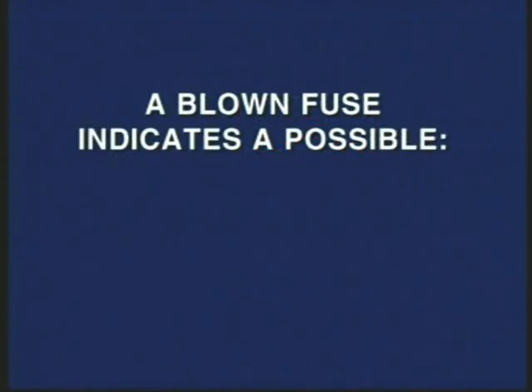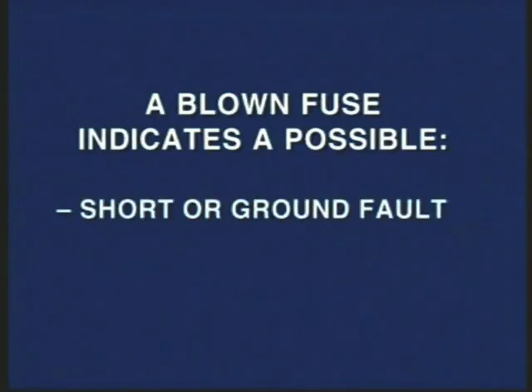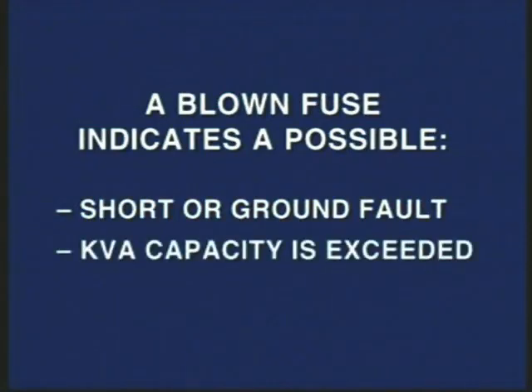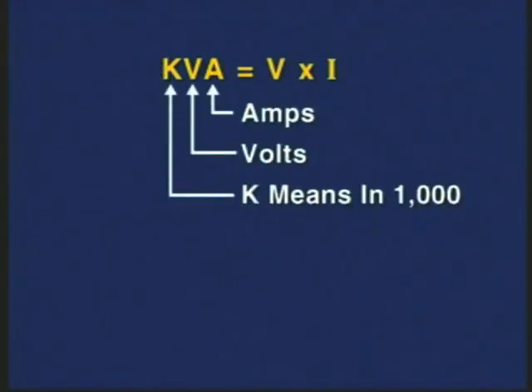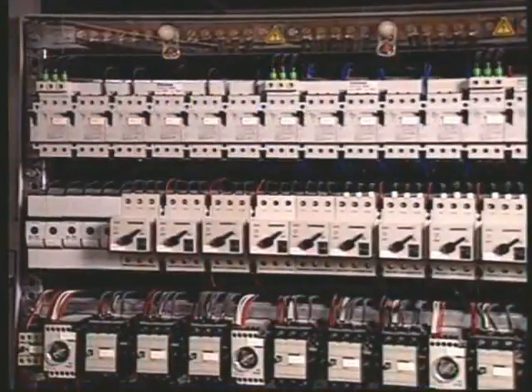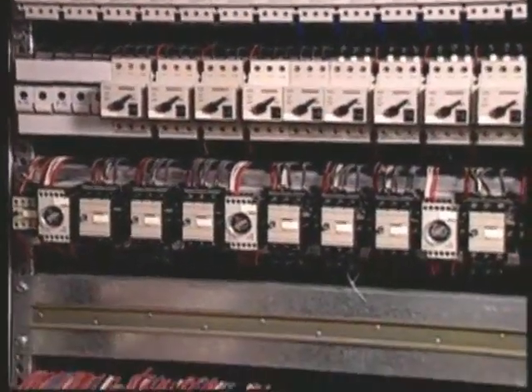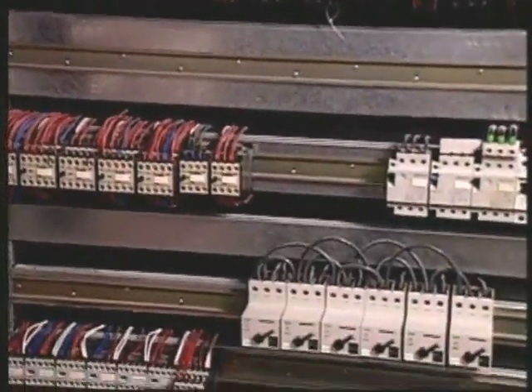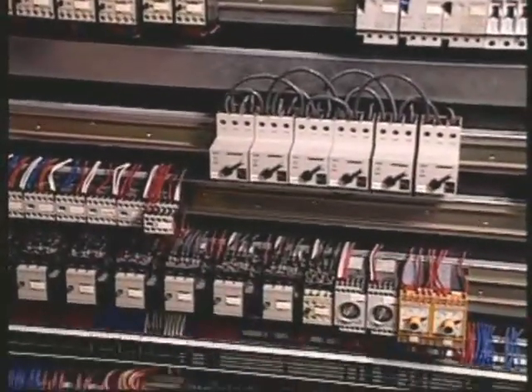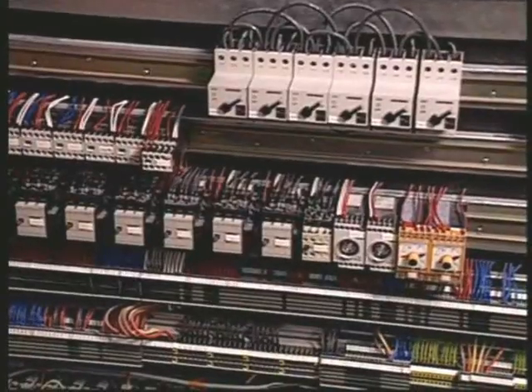However, this condition could indicate that a possible short or ground fault could have occurred in the control circuit, thus blowing the fuse, or that the kVA power of the transformer was too small for the number of loads in the circuit. As we know, a transformer is rated for a specific kVA, which is the voltage times the current it can supply. The loads of the control circuit may be composed of a number of relays, counters, timers, starter coils, solenoids, and others, which could overload the transformer and reduce the voltage and increase its current to a point which could even blow the fuse.